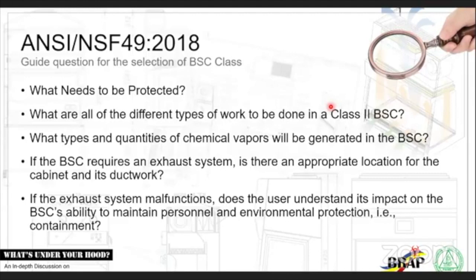What are all of the different types of work to be done in the biosafety cabinet? Again, the process. The third question: what types and quantities of chemical vapors will be generated in the biosafety cabinet? Now, this is a very good question. So we not only focus on the biological part, but also the materials that we are handling. So if you plan to do, for example, sample inactivation and you're using a toxic chemical, you might want to look into a system that has ducting to exhaust room air and biosafety cabinet air, right?